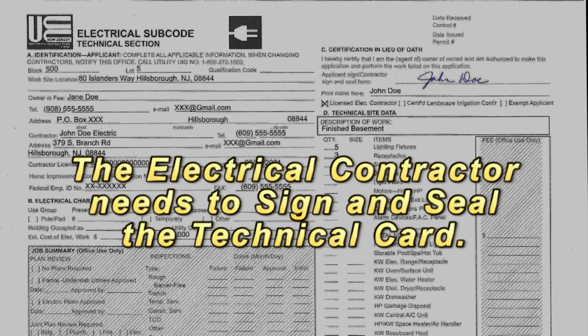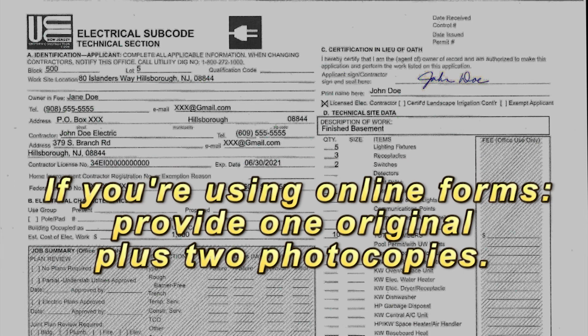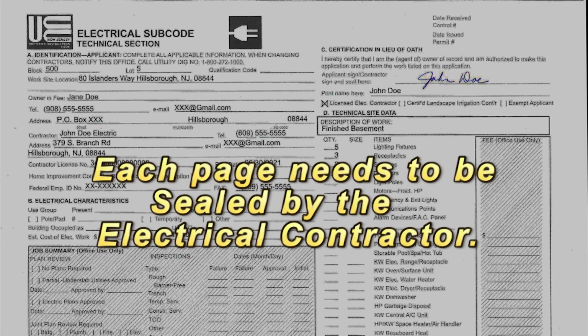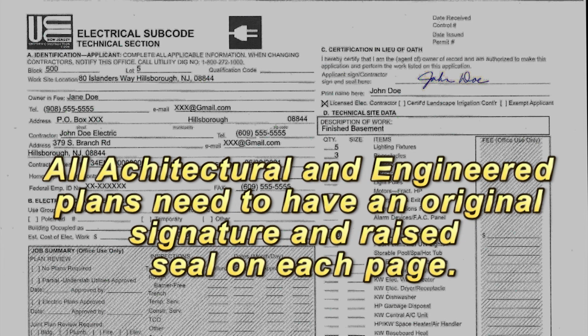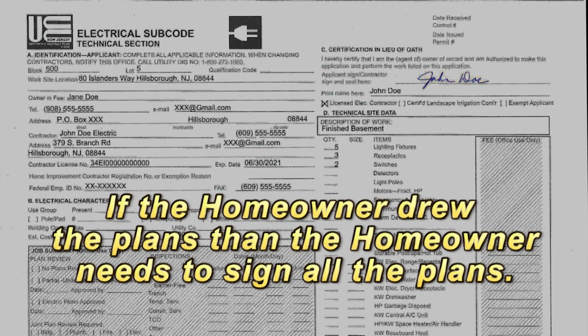When submitting an electrical subcode technical section, the electrical contractor needs to sign and seal the technical card. If you are using online forms, provide one original plus 2 photocopies, but each page needs to be sealed by the electrical contractor. Just to repeat, each page needs to be sealed by the electrical contractor. All architectural and engineered plans need to have an original signature and raised seal on each page. If the homeowner drew the plans, then the homeowner needs to sign all the plans.